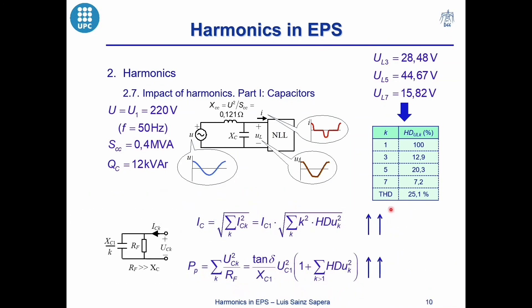The increase of the harmonic voltages due to this resonance at the fifth harmonic may produce overloading and overheating problems in the capacitor bank.